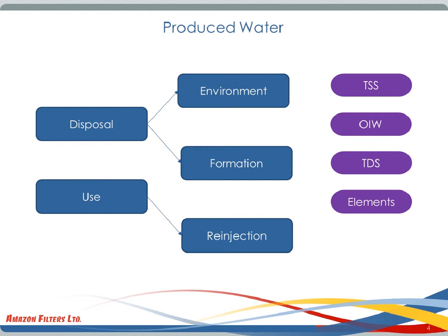Additionally, there are requirements and controls on certain elements that are within that produced water for disposal, such as mercury. And also, another problem is NORM, or naturally occurring radioactive material. This occurs naturally in the Earth's crust and can build up in scale deposits inside the pipework, which then becomes detached and is present in the produced water. There will be environmental restrictions on what levels of background radiation we can dispose of into the environment, so that scale will need to be collected as part of the suspended solids, where it can then be suitably disposed of in a safe environment.